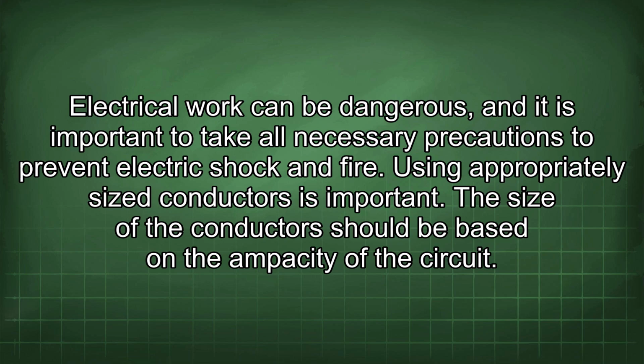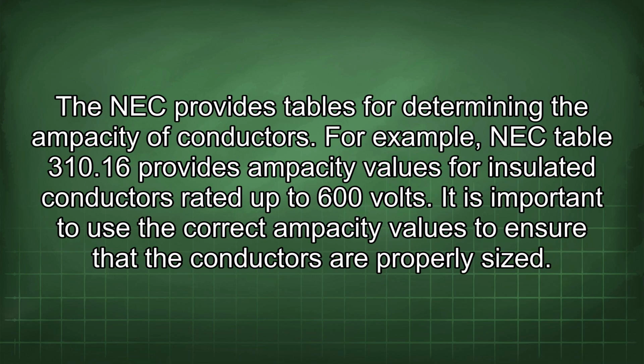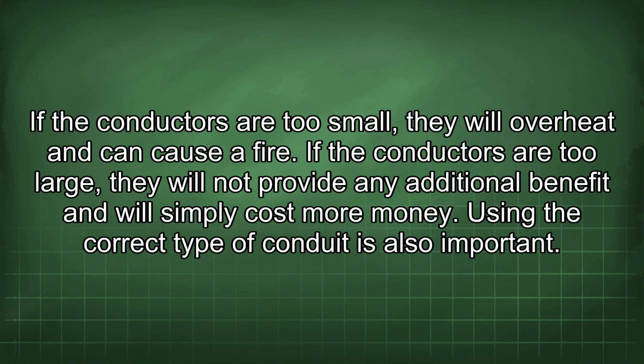Using appropriately sized conductors is important. The size of the conductors should be based on the ampacity of the circuit. The NEC provides tables for determining the ampacity of conductors. For example, NEC Table 310.16 provides ampacity values for insulated conductors rated up to 600 volts. It is important to use the correct ampacity values to ensure that the conductors are properly sized. If the conductors are too small, they will overheat and can cause a fire. If the conductors are too large, they will not provide any additional benefit and will simply cost more money.